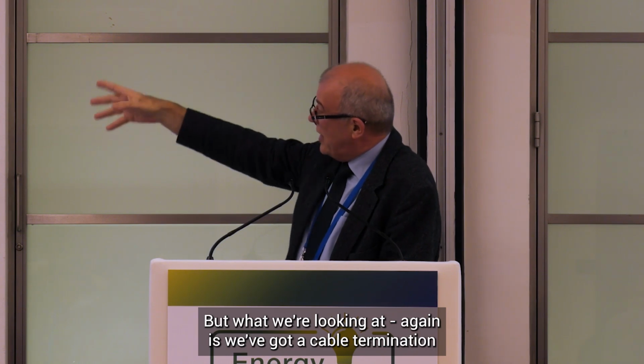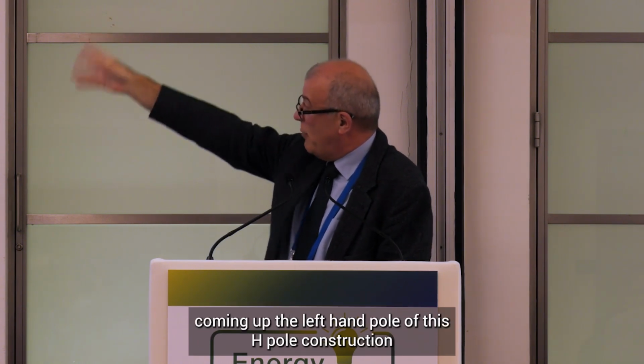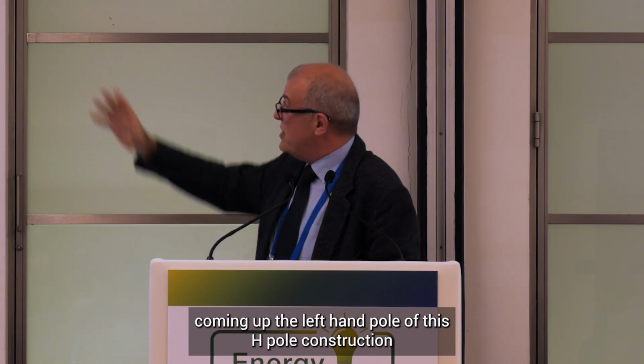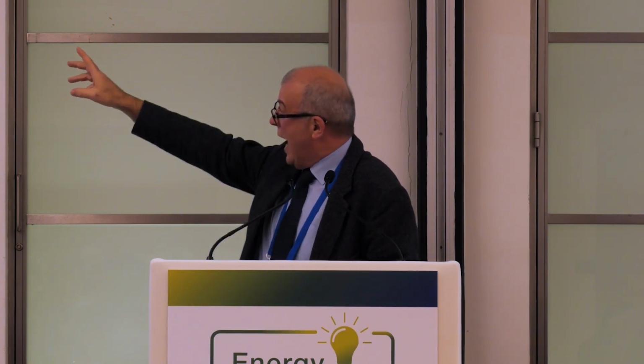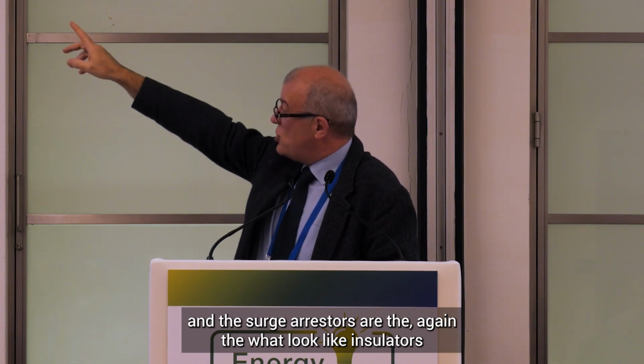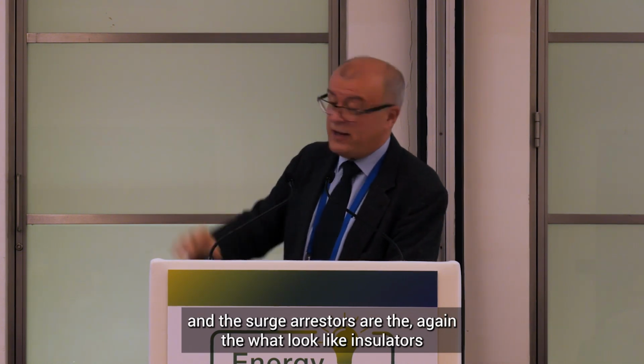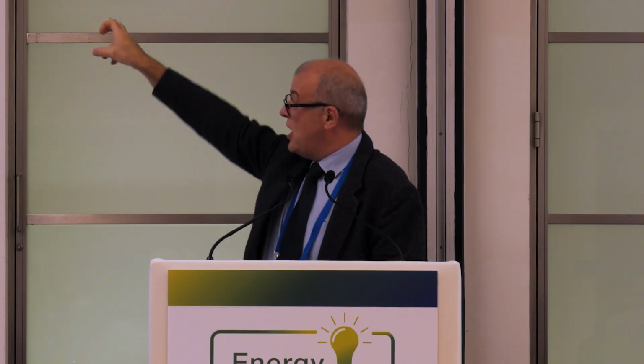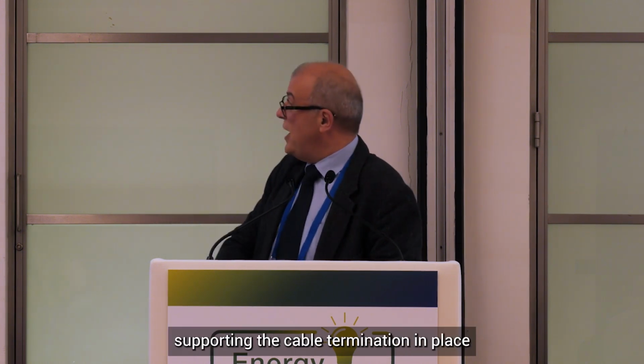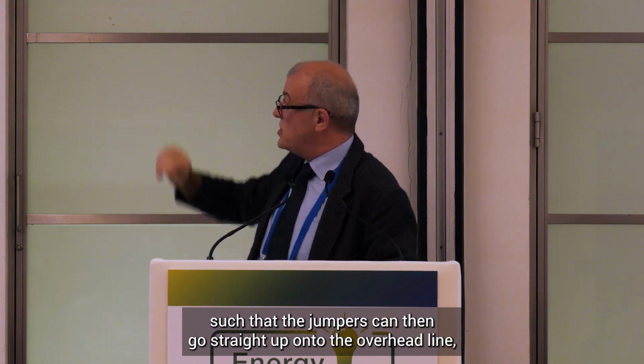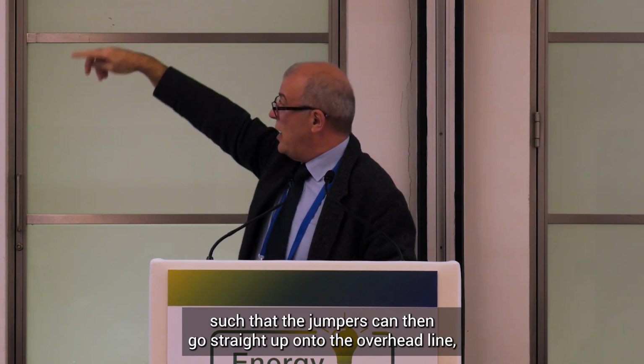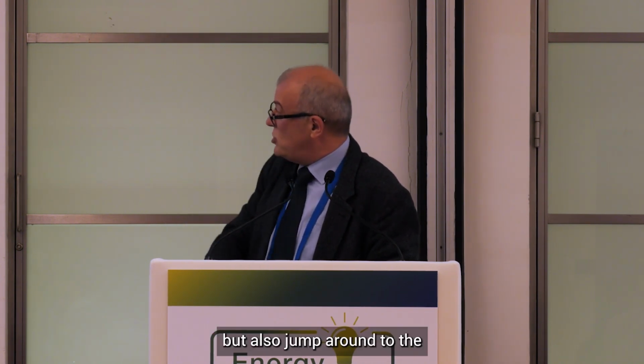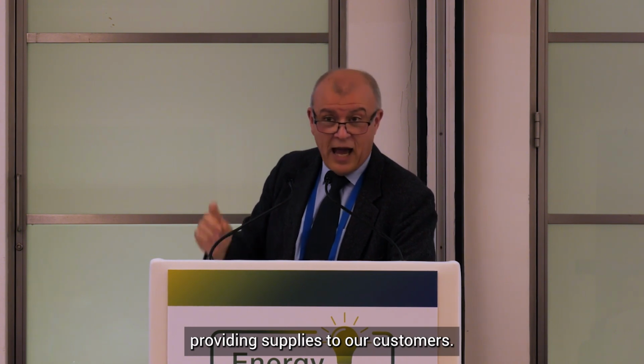But what we're looking at, again, is we've got a cable termination coming up the left-hand pole of this H-pole construction. And the surge arrestors are what look like insulators coming off the crucifix, supporting the cable termination in place such that the jumpers can then go straight up onto the overhead line, but also jump around to the transformer, providing supplies to our customers.